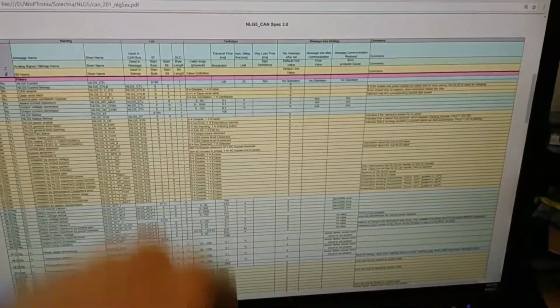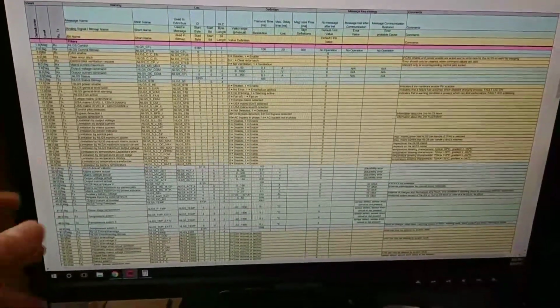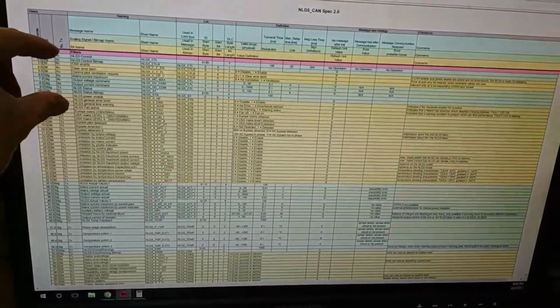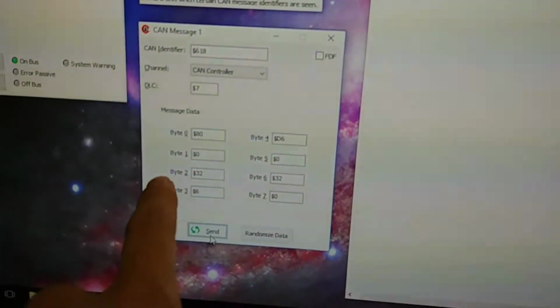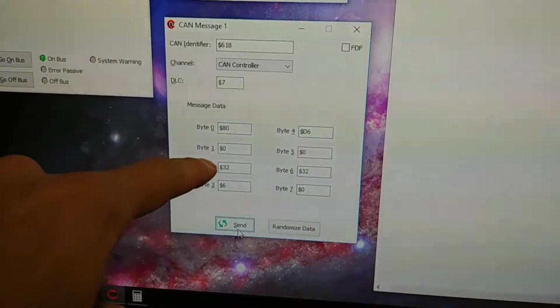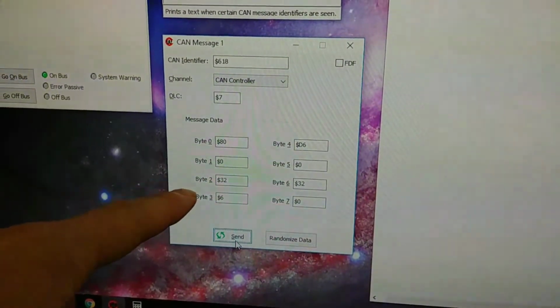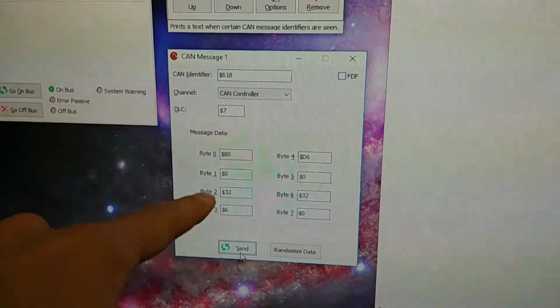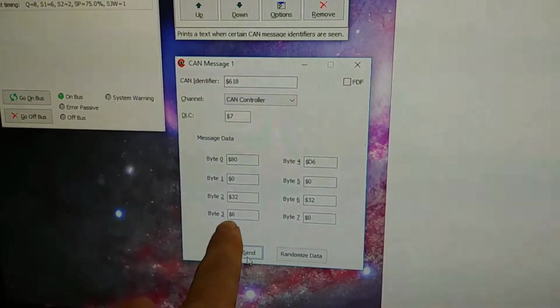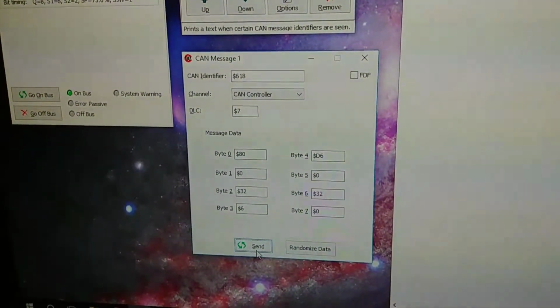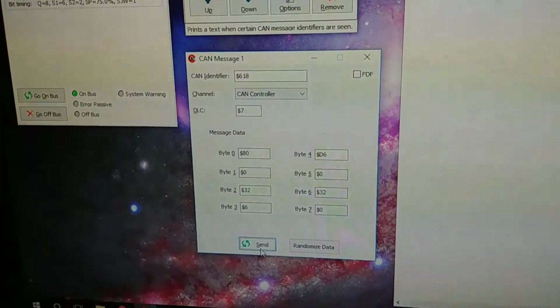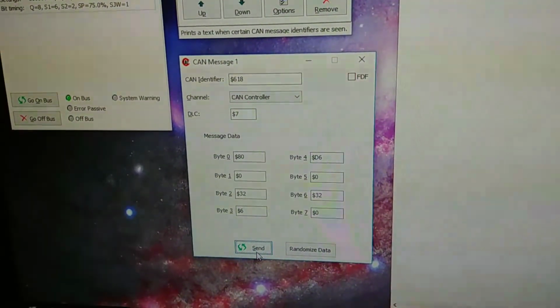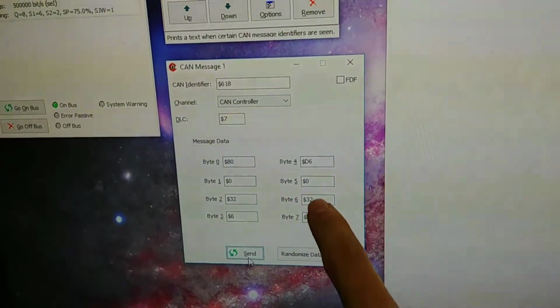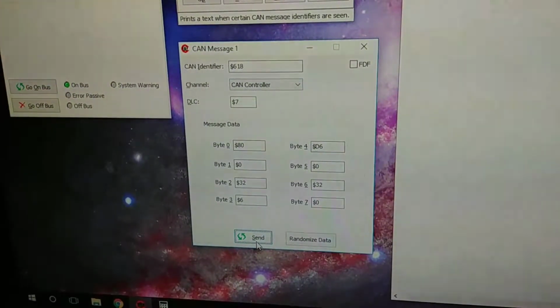Over on the CAN side, they're kind enough to give us the full CAN spec for the NLG5. So this is the entire CAN listing, and I've filled out the receive section that I have to transmit to it, and I can show you what I'm commanding. The 80 hex tells it to enable the charger, and the 032 is commanding 50 in decimal, which times 0.1 is asking for 5 amps max current from the mains. The next two bytes, 6D6, is 1,750, but again times 0.1, so in reality I'm asking for 175 volts DC. Then 0032 again is 50 in decimal, asking for 5 amps.